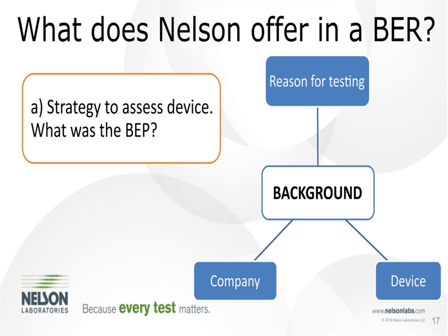Now let's go over how we address all the points in ISO 10993-1 for a BER. The blue diagram on the right shows section titles in the center block, with information contained in each section in the outer blocks, and the relevant part of ISO 10993-1 identified in orange. Our first section is the Background — we provide the back story on the company, the device, and why this is being submitted. This references back to the BEP, laying out what's going on.